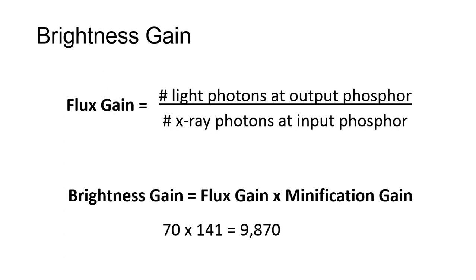Flux gain is also used to calculate total brightness gain. If you recall, flux gain was the ratio in the number of light photons at the output phosphor to the number of x-ray photons at the input phosphor. Your textbook gives us an example where a particular flux gain for an image intensifier is equal to 70.